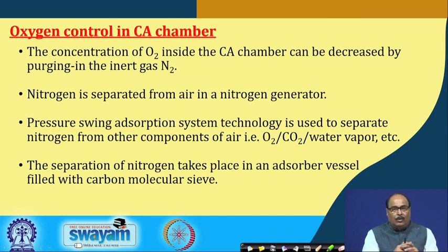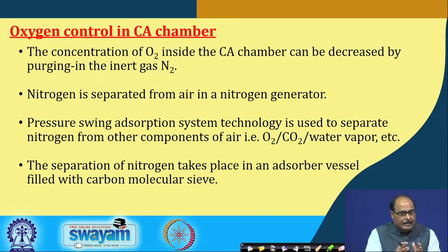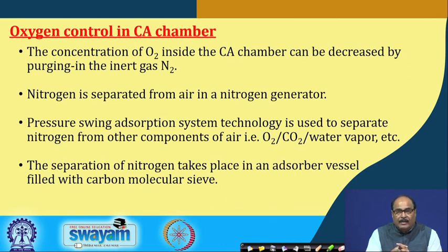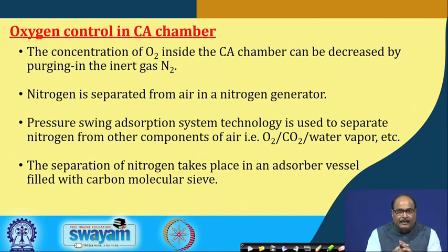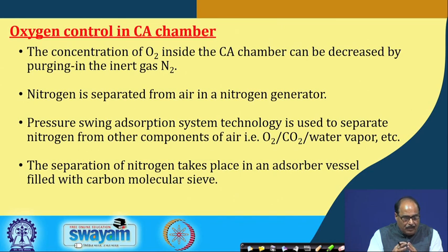From these three considerations one can calculate the total cooling load of the refrigeration unit. The second aspect is oxygen control in the control atmosphere chamber. The concentration of oxygen inside the CA chamber can be decreased by purging in the inert gas nitrogen, and nitrogen is separated from air in a nitrogen generator. Pressure swing adsorption (PSA) technology is generally used to separate nitrogen from other components of air — O2, CO2, or water vapour. The separation of nitrogen takes place in an adsorber vessel filled with carbon molecular sieves (CMS).